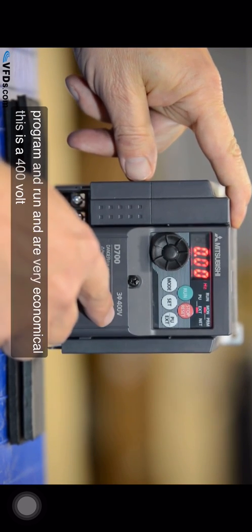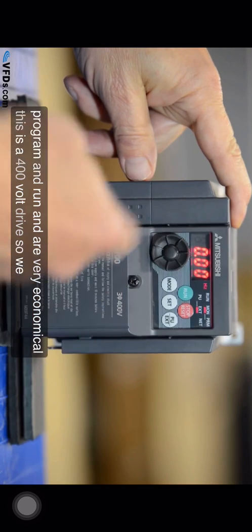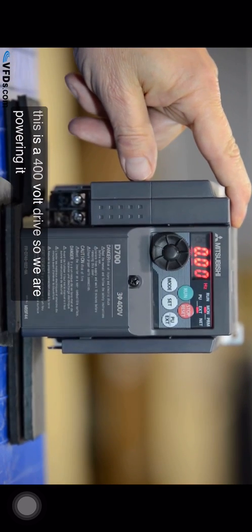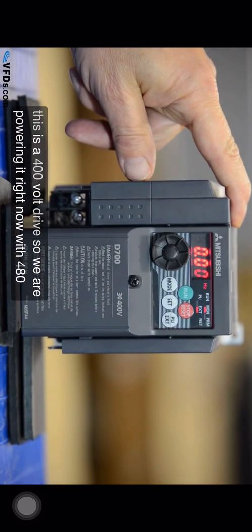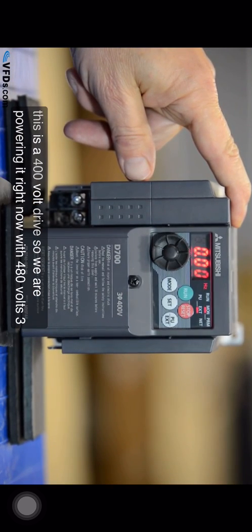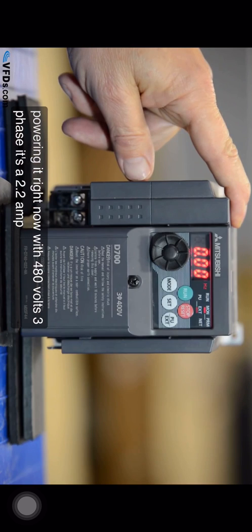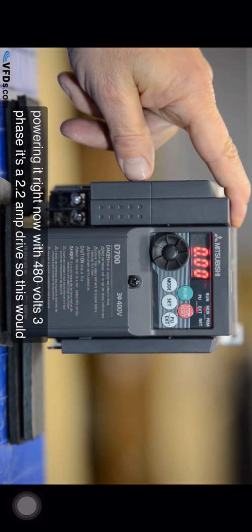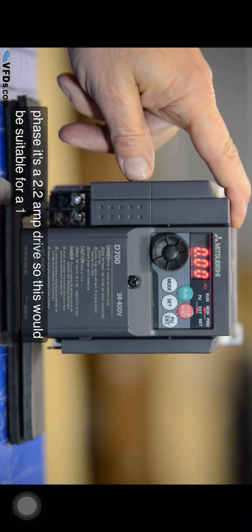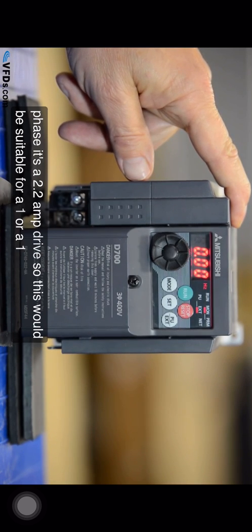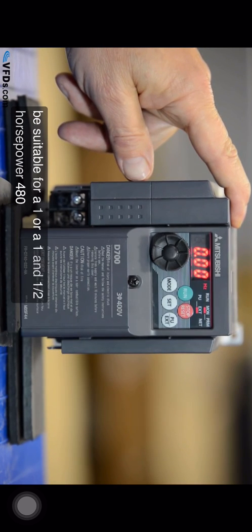This is a 400 volt drive so we are powering it right now with 480 volts three phase. It's a 2.2 amp drive so this would be suitable for a one or one and a half horsepower 480 volt motor.